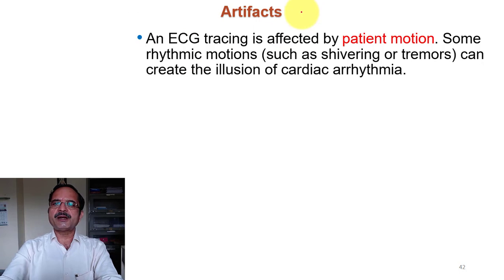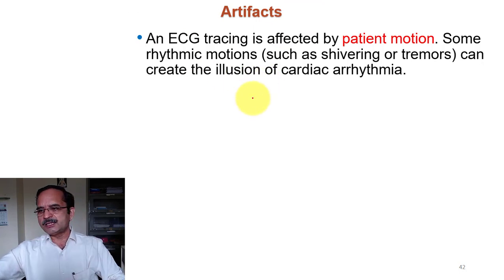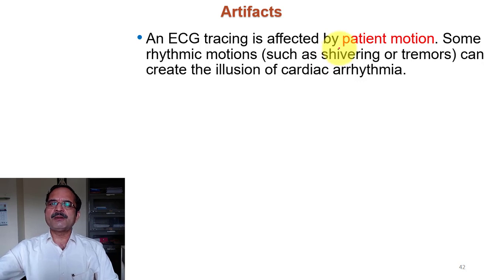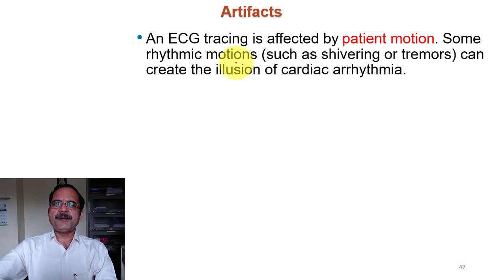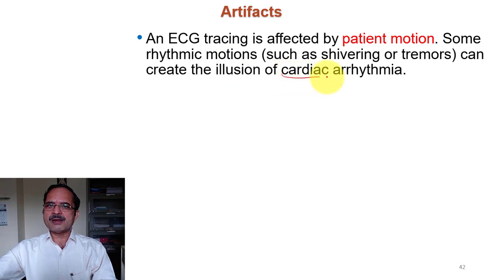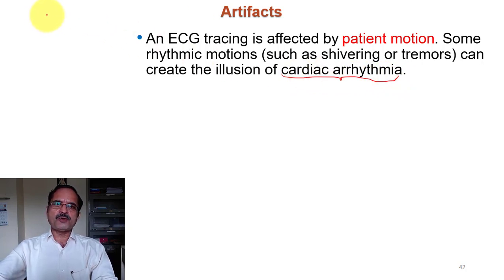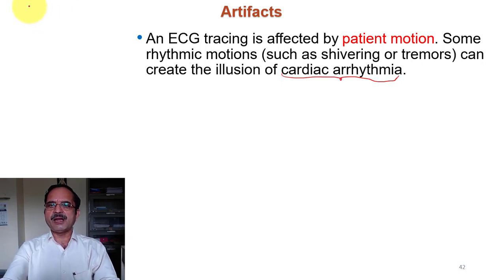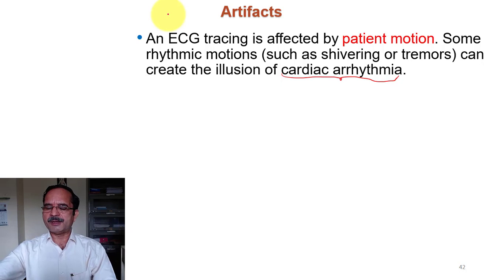The ECG tracing is affected by patient motion. When measuring the ECG waveform by placing electrodes on the body of the patient, there will naturally be some motion by the patient, and because of that, some artifacts or noise is produced. This may give the illusion of cardiac arrhythmia — because of noise, some different type of pulse may be present, and the doctor may predict it as some irregularity in the beating of the heart.